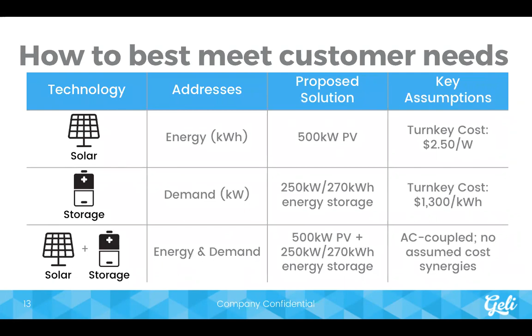And then finally, what if we install both solar and storage at this customer site - combining that 500 kilowatt PV system with a 250 kilowatt energy storage system? We'll talk about the implications of that. Solar addresses the energy, storage addresses the demand, and together we'll see how the results play out to be either better or worse than the individual components.